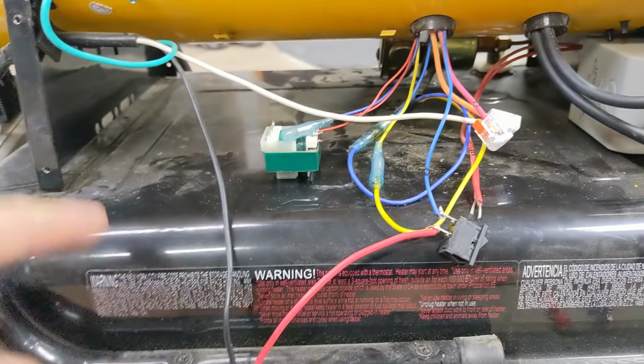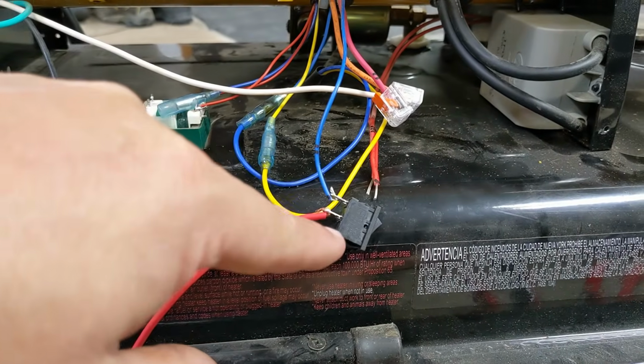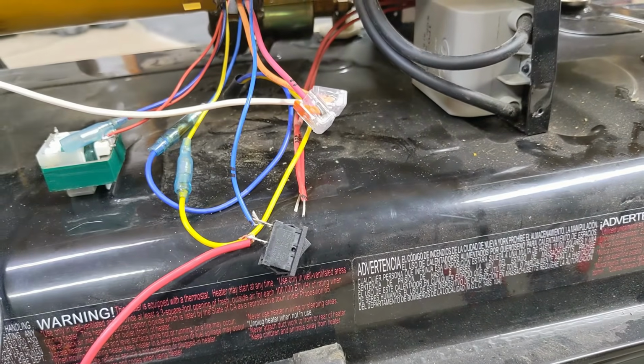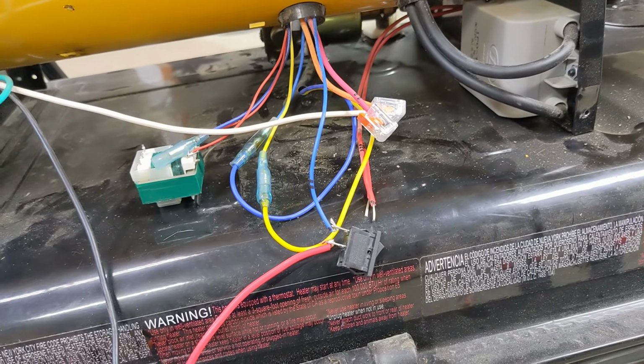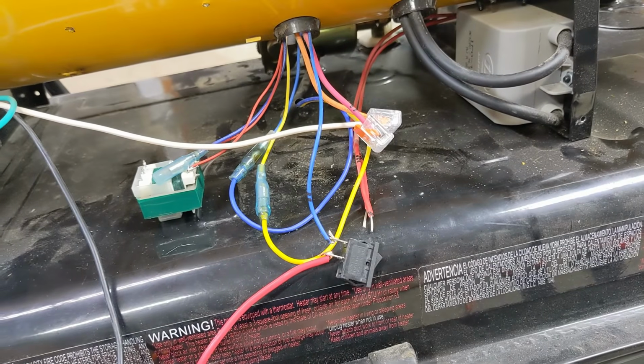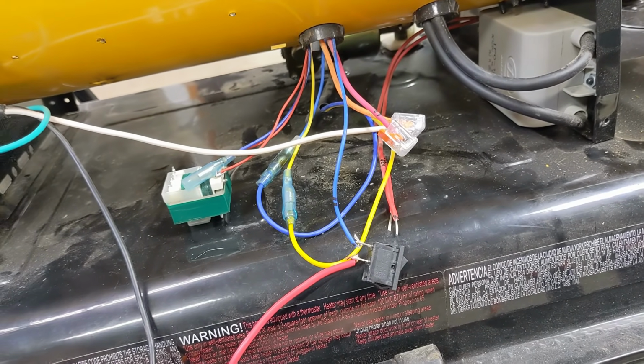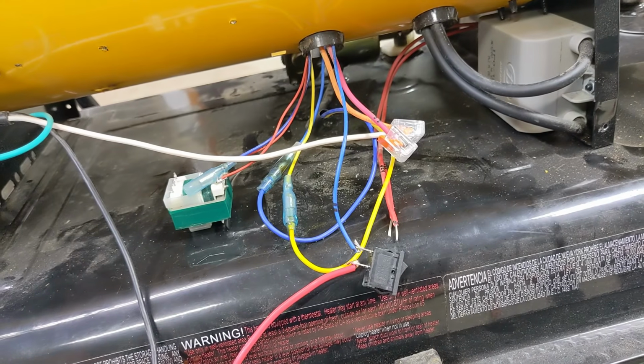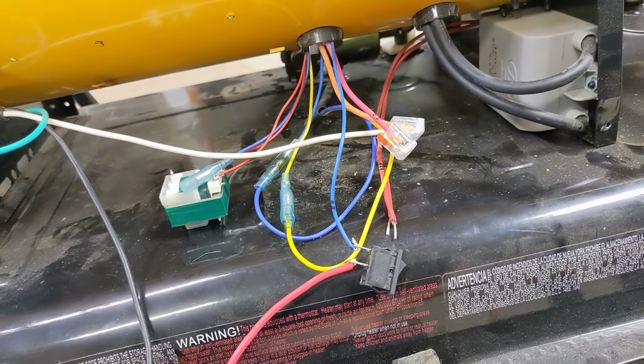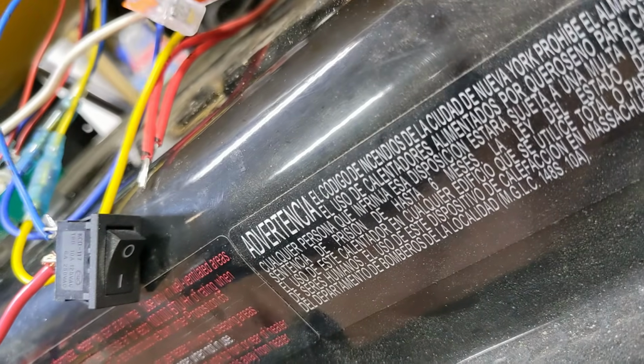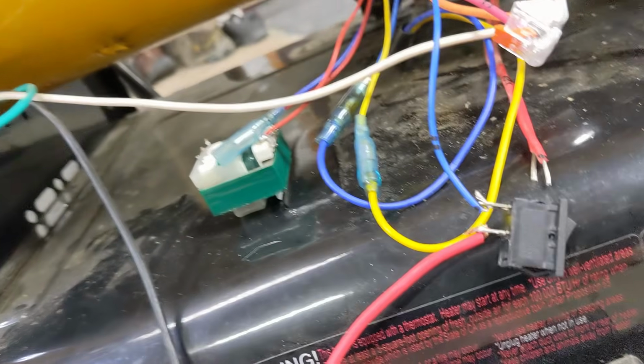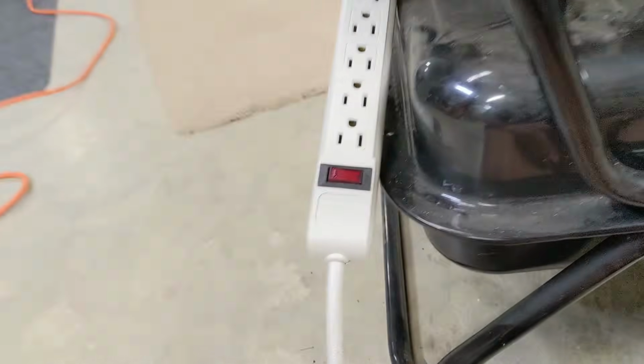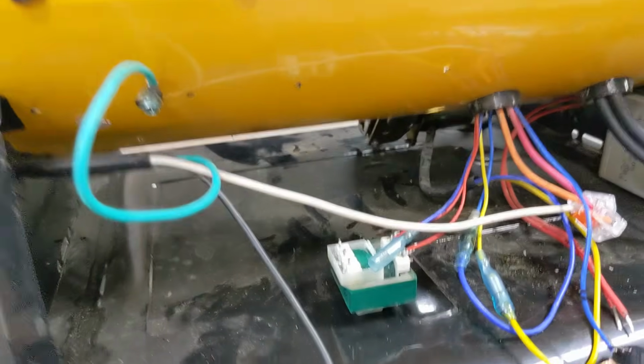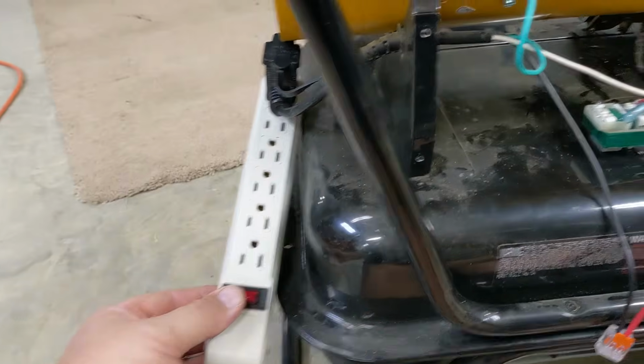So what I'm saying is I sent the hot to the switch. The other side of the switch goes through that temperature sensor probe thingy, comes back and goes over to the pump. So the pump has a yellow and a blue wire feeding it AC. Yellow is the neutral, the blue is the hot wire if you want to call it that. I just turned the switch on because I don't want to fiddle with it when it's live with juice in it. So this should turn on only the fuel pump, the solenoid is off. Let's see if it does it.